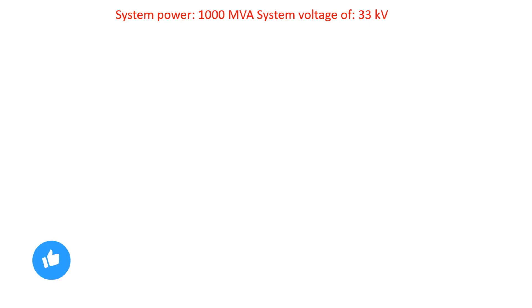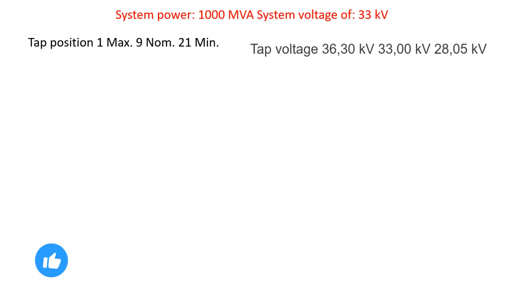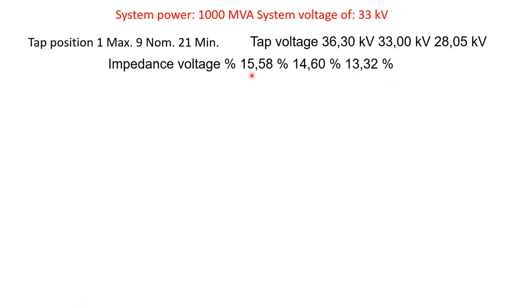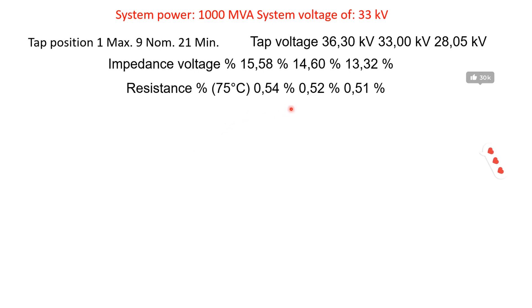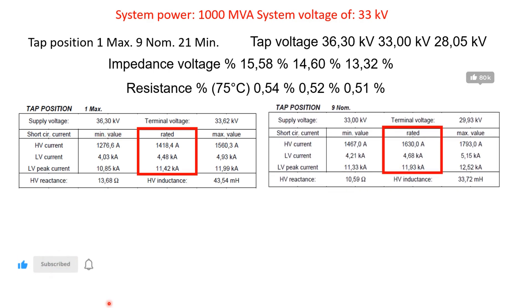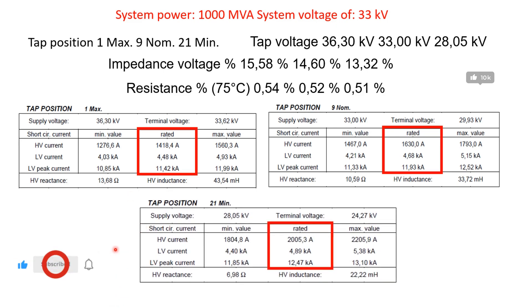Here is an example: system power 1000 MVA, system voltage 33 kV. Tap positions are: tap 1 maximum, tap 9 nominal, tap 21 minimum. Tap voltages are 36, 33, 28.05 kV. Impedance voltage values are 15.58 percent, 14.60, and 13.32 percent. Resistance at 75°C: 0.54, 0.52, and 0.51. The table shows all information based on each tap position, including tap-changing position data, all based on the 33 kV, 1000 MVA rating.